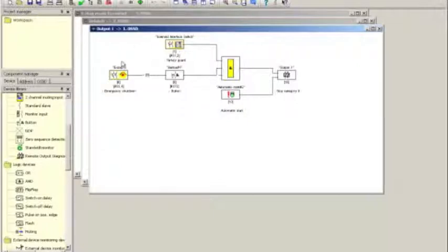A couple of things I want to go through. First is the definition or the logic that is utilized for controlling motor 1, the safe output 1, that then connects to the safety contactor. So what I have here is the solenoid interlocking switch run into my global AND, and I have an e-stop. And for a reason that's not immediately evident, I will utilize what is called a button device, and I use this button device in conjunction with the input contact S72 on the safety controller.